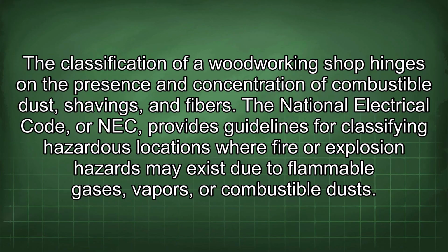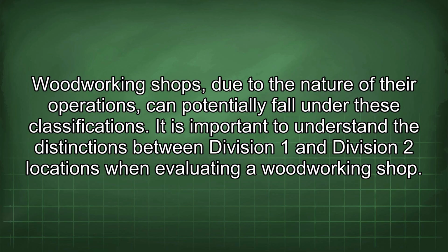Classification of a woodworking shop hinges on the presence and concentration of combustible dust, shavings, and fibers. The National Electrical Code, or NEC, provides guidelines for classifying hazardous locations where fire or explosion hazards may exist due to flammable gases, vapors, or combustible dusts. Woodworking shops, due to the nature of their operations, can potentially fall under these classifications. It is important to understand the distinctions between Division 1 and Division 2 locations when evaluating a woodworking shop.